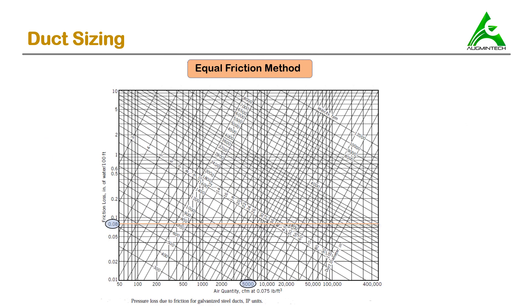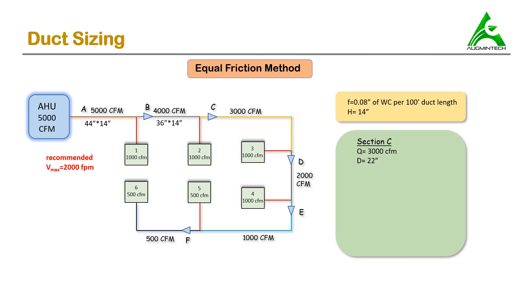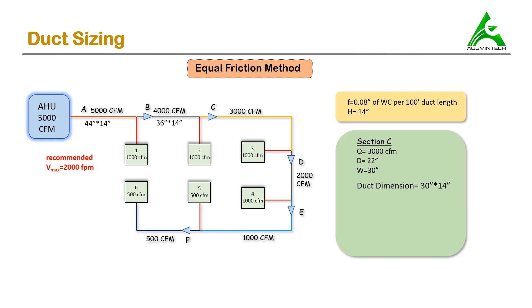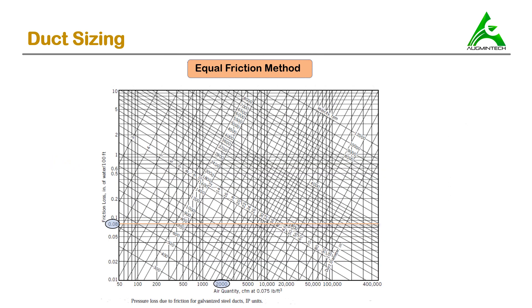For section C, the airflow rate is 3000 CFM. Using the chart, the intersection gives a diameter close to 22 inches. From the conversion chart, 22 inch diameter with 14 inch height gives a width of 30 inches. The duct dimensions for section C are 30 inches by 14 inches. The aspect ratio is 2.14, which is less than 4, so this is accepted.